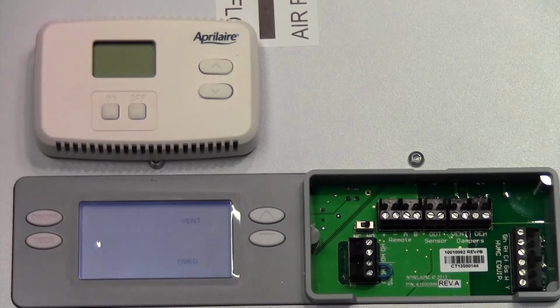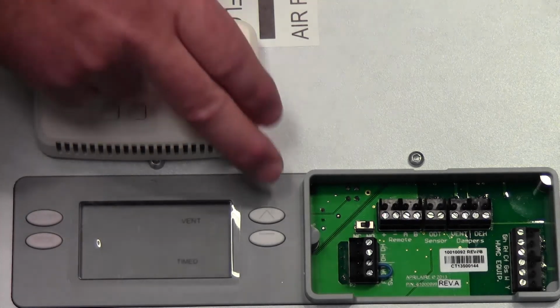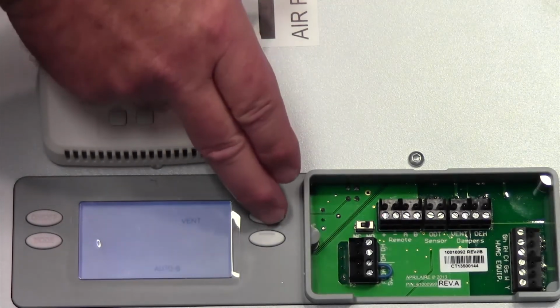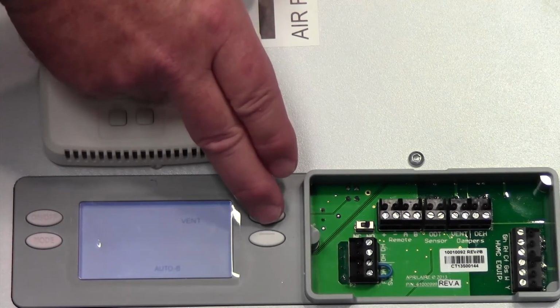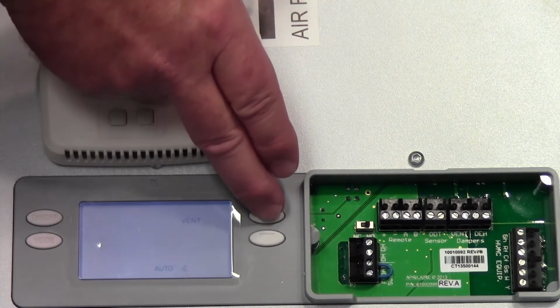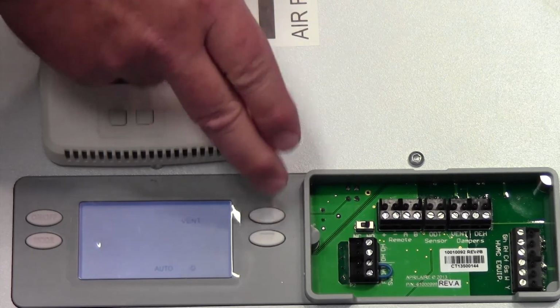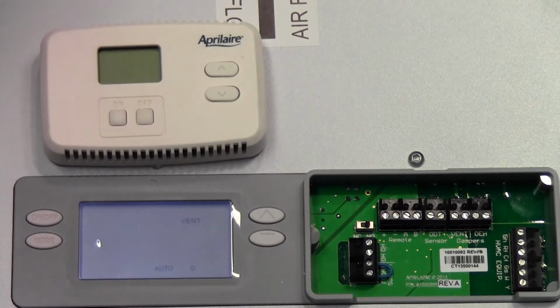Vent timed would be like our ASHRAE timed. If we're doing it per code and we have to have so many minutes in an hour, no matter what happens, that's what it'll be. We also have the ability to set this up in our Auto B, Auto C, and Auto D modes. If you're familiar with our Model 8126A ventilation system, this has the exact same parameters as that.